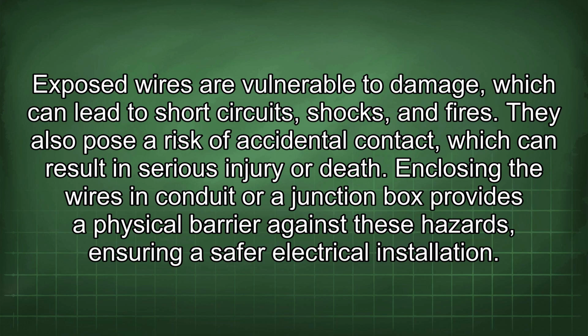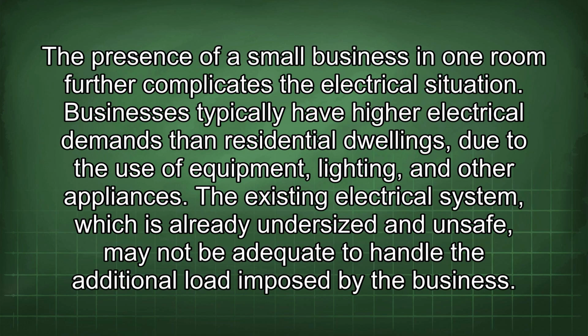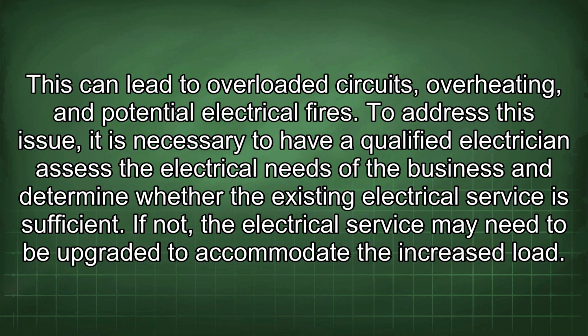Enclosing the wires in conduit or a junction box provides a physical barrier against these hazards, ensuring a safer electrical installation. The presence of a small business in one room further complicates the electrical situation. Businesses typically have higher electrical demands than residential dwellings due to the use of equipment, lighting, and other appliances. The existing electrical system, which is already undersized and unsafe, may not be adequate to handle the additional load imposed by the business. This can lead to overloaded circuits, overheating, and potential electrical fires.